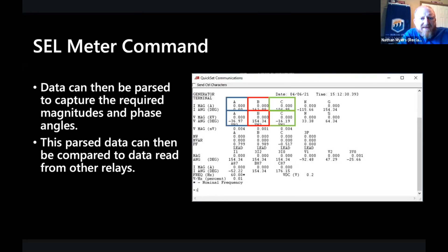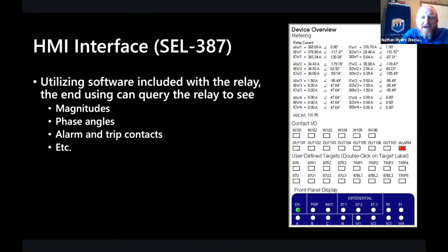As I mentioned, that's when the data can be parsed. We'll look at the magnitudes and phase angles, and we'll ensure that the data is similar. Next. They also have HMI interfaces. That's what this is an example of. And again, you can see basically we're looking at magnitudes, phase angles, alarms, and trip contacts as well. So the communications with the relays are fairly easy. Downloading these settings isn't overly challenging. It can be done through automated methods. We do that for relay testing at the moment to a certain extent, but not to the extent that we're looking to do right now.